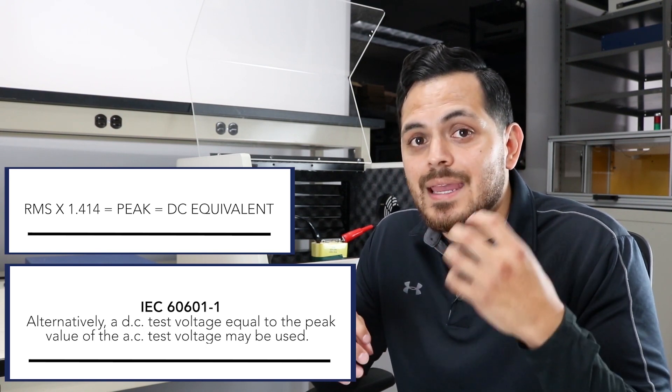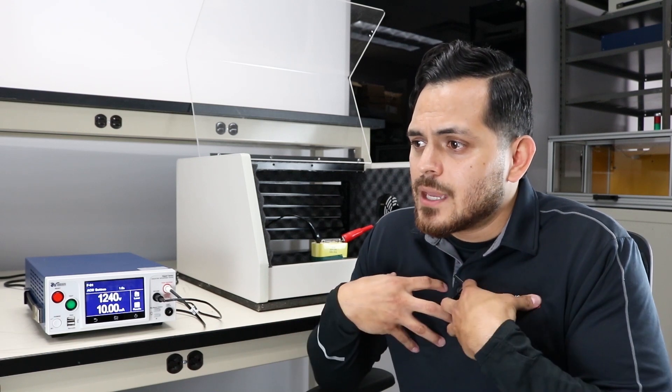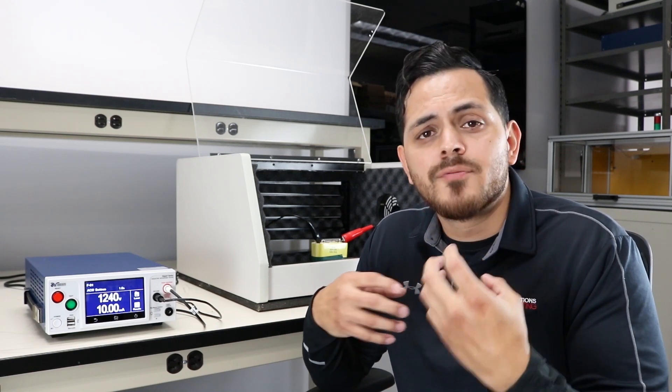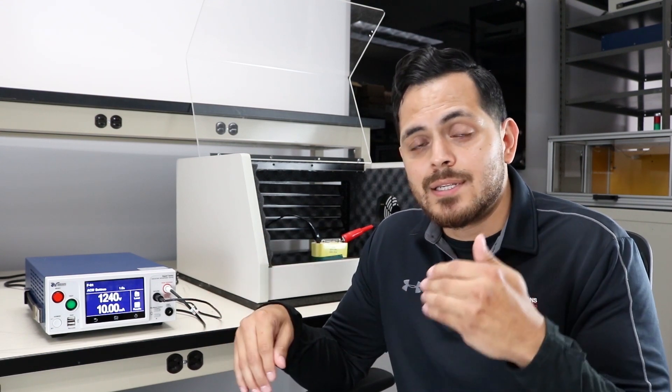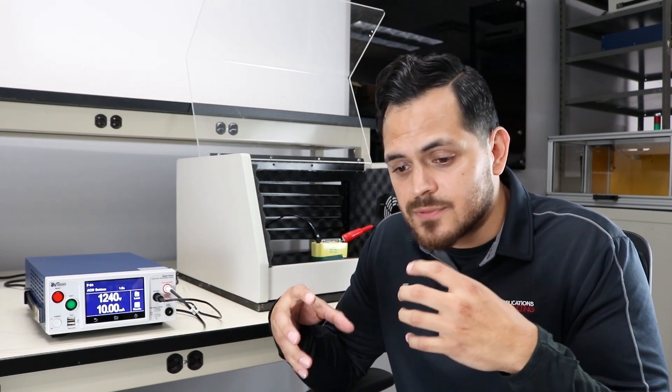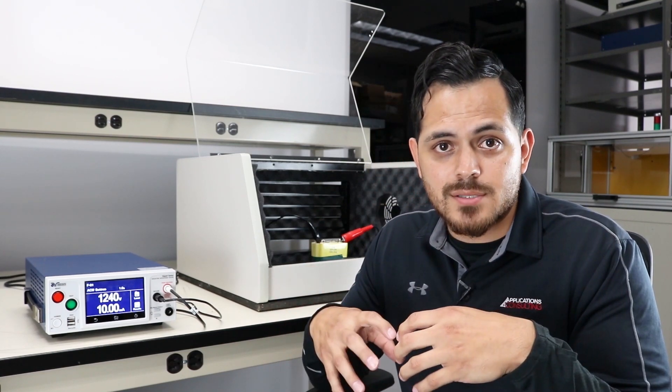What that's saying is if I was running a 1200 volt AC hypotest, I can't just turn it into DC at that same value. I need to make sure that insulation is feeling the exact same stress as it would in the AC hypotest, so I need to use that peak value for my DC hypotest.